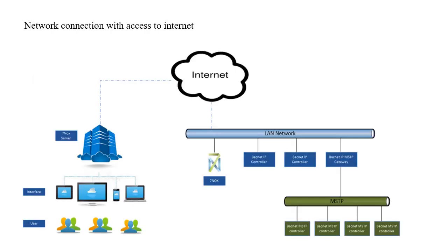This diagram demonstrates a typical 7Nox implementation architecture, where the users connect over the Internet to the 7Nox hosted service, which in turn communicates with the 7Nox site device located on the client side. The 7Nox site device communicates using HTTP protocol to connect to the 7Nox hosted service, which is a cloud-based service. The 7Nox site device located on site communicates over the local network using BACnet protocol to enable the after-hours air conditioning via the BMS control system.